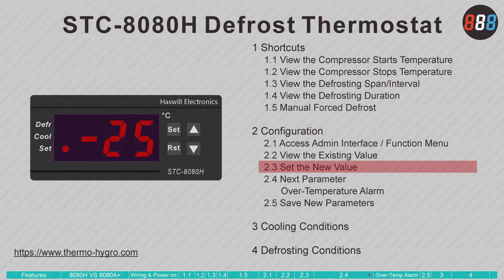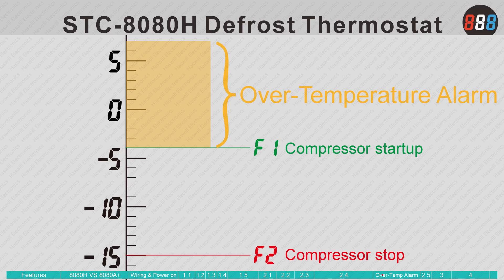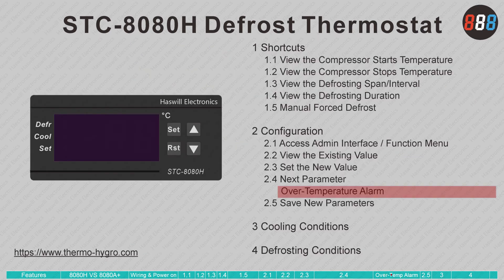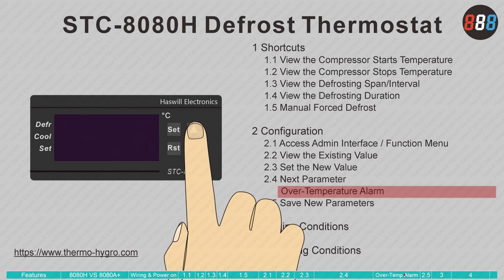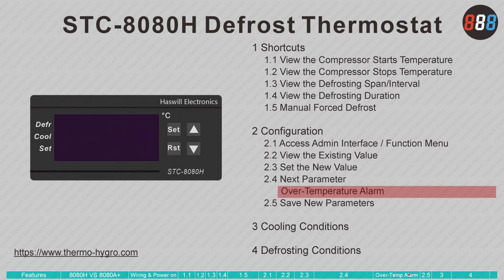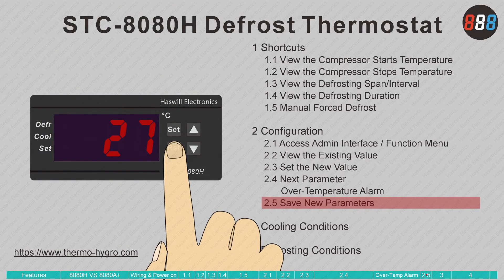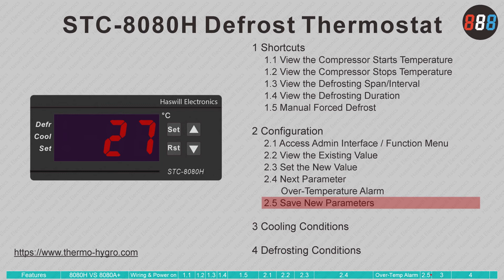Most parameters are straightforward, but note that the over-temperature alarm in the STC-8080 refers to how many degrees above F1 it is — not the absolute temperature at which the alarm occurs. When the over-temperature alarm triggers, the device sounds an alert and the reading flashes on the display. You can press any key to stop the sound, but the reading will not stop flashing until the room sensor temperature returns to the safe range. After configuring all menus, press the RST key to save and return to normal state.